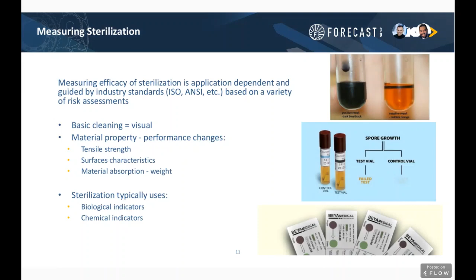Next up, if we were going to walk through sterilizing a 3D printed component, essentially you would start on the left-hand side by picking your application and identifying an industry standard to use as either our guideline or as the actual guideline for your product. From there, you typically verify the technology and material. Sometimes the OEMs actually supply some of this information, depending on what your actual application is. There might be information available to you. In some cases, depending on what you're doing, you actually have to do your own studies and confirm and verify that this is going to work for your situation.